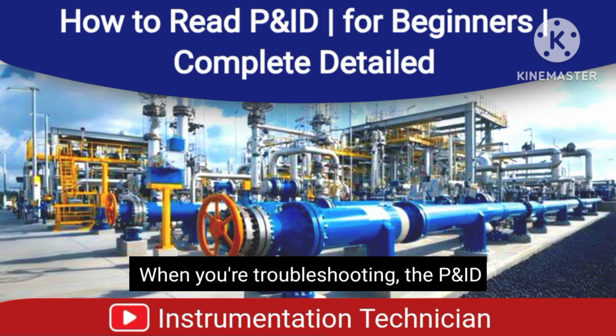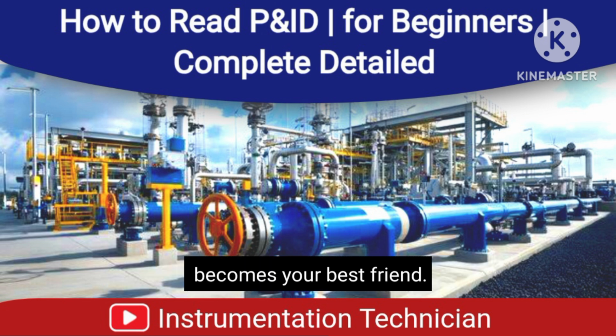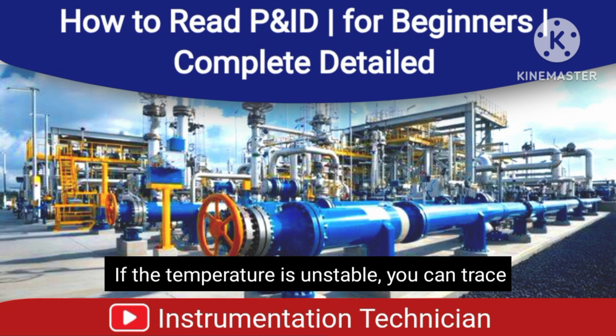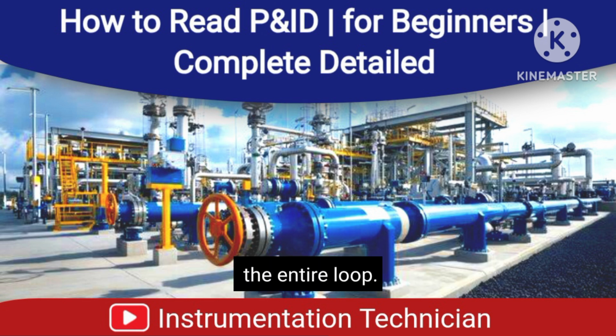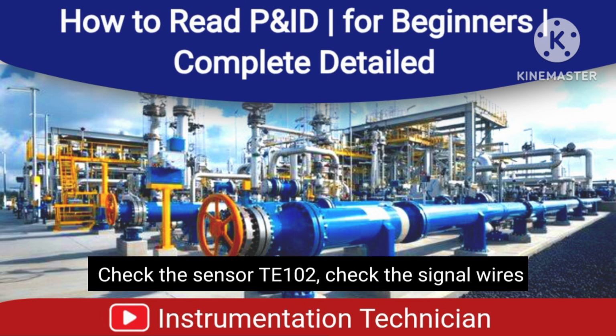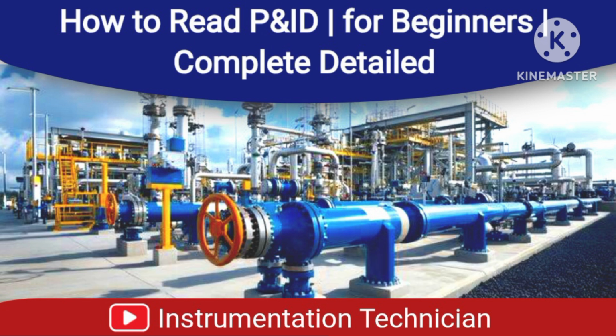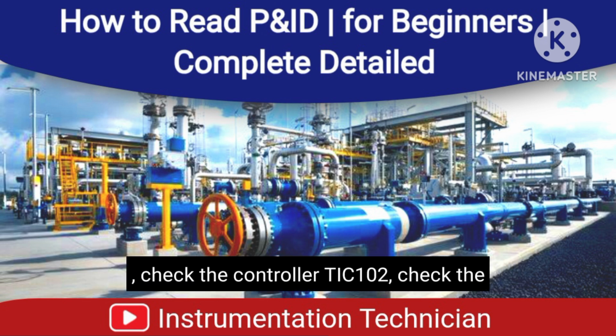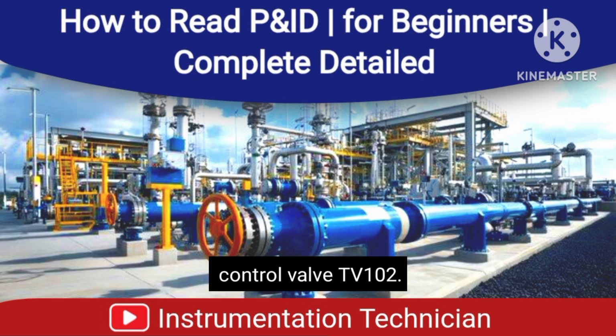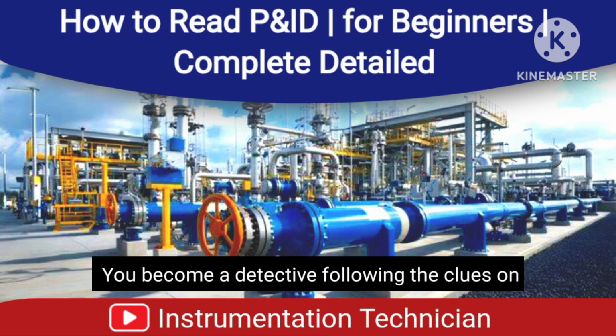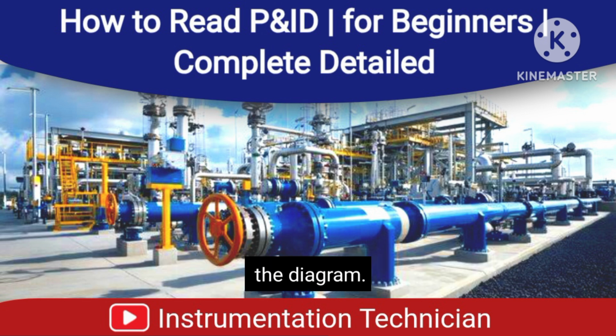When you're troubleshooting, the P&ID becomes your best friend. If the temperature is unstable, you can trace the entire loop. Check the sensor TE102, check the signal wires, check the controller TIC102, check the control valve TV102. You become a detective following the clues on the diagram.